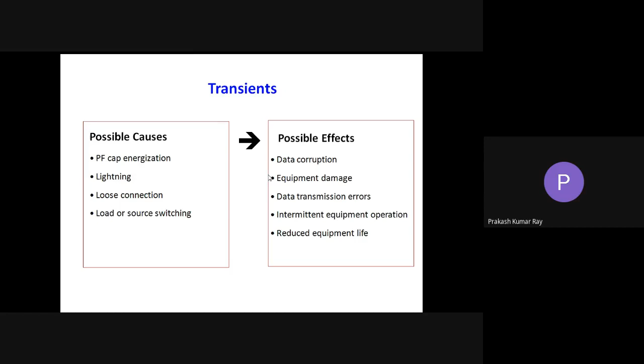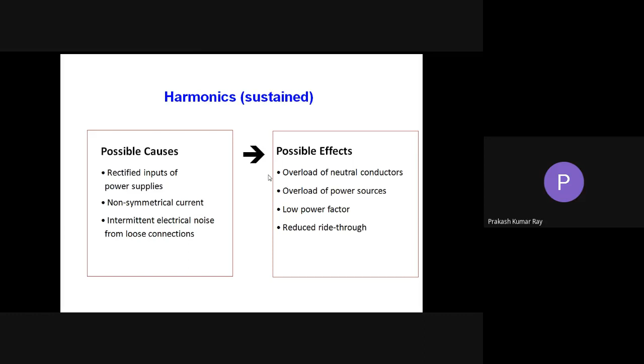Harmonics is another important type of power quality event. That is because of power electronic based loads or nonlinear loads. It will lead to overload of neutral conductors, overloading of power sources, low power factor, and reduced ride through capability. So the power system will be affected in some way by these power quality disturbances.